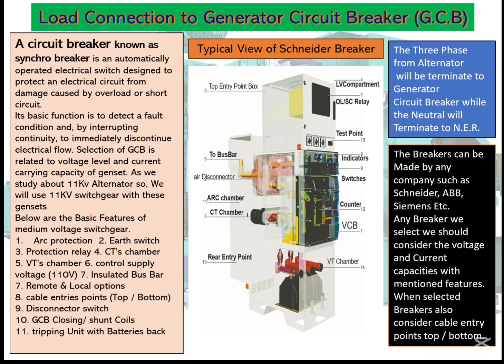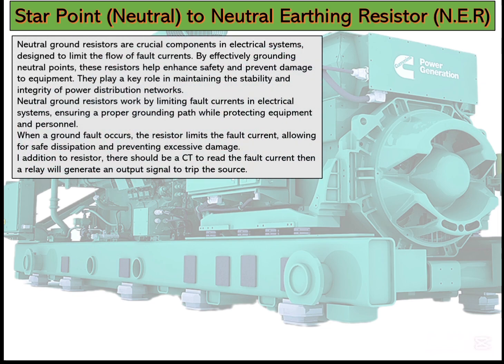Then at LV, the neutral is not an issue. You can just connect the neutral direct to the load. But when it comes to high voltage, either alternator or transformer, the neutral should pass through a neutral earth resistor. If there is any fault, any short circuit, any arc fault on the customer end or load end, the fault always travels towards the source. So before it damages the alternator, the current should be limited.